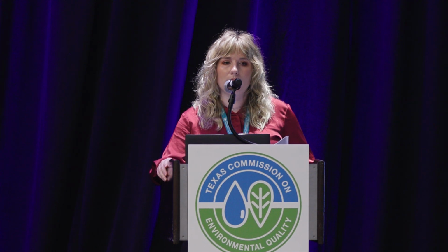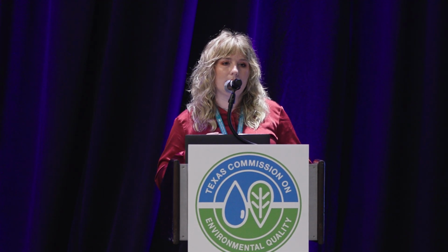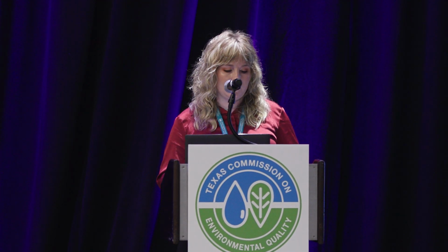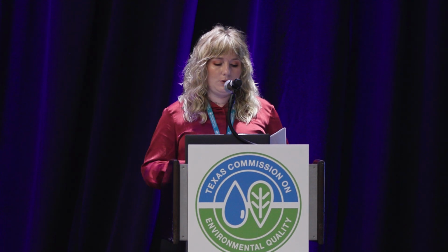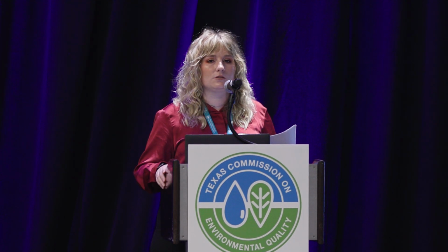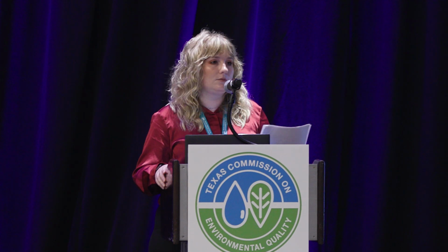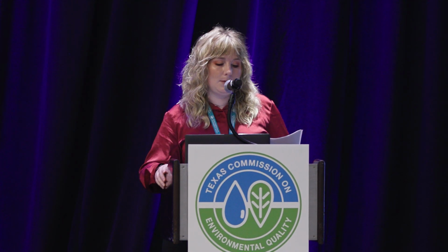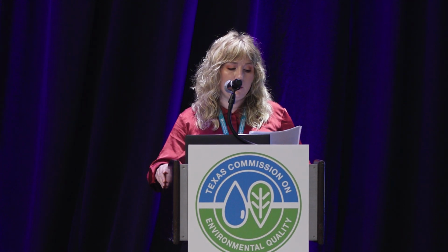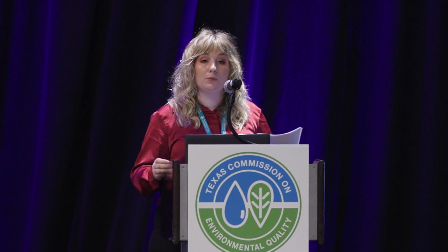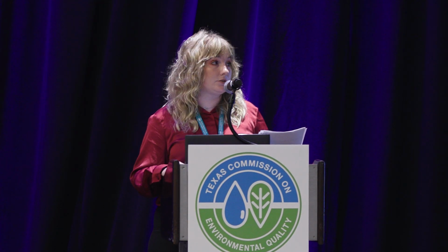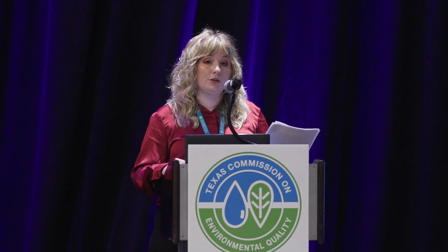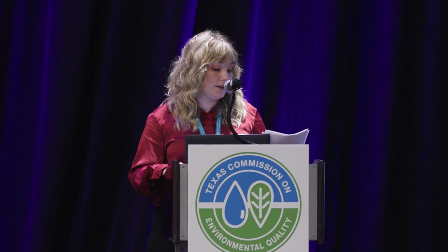A good example of how this is helpful is, say you have a system with an entry point of 1.5 milligrams per liter. It's usually around there. It doesn't waver too much because you're good on your dosage. You know that the house all the way at the end of your distribution is probably testing around 0.85, maybe 0.83. One day you get a reading of 0.0 at your house on the end of that distribution system. However, you know your entry point is still at 1.5.